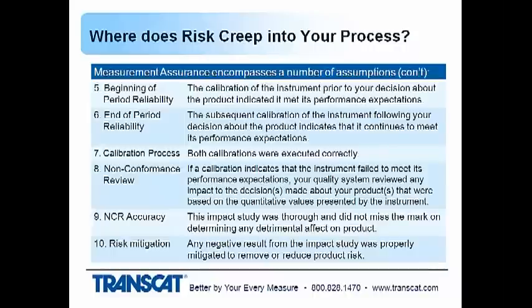Following the calibration, your non-conformance review. If your instrument failed to meet its performance specs, then your quality system probably has a review process in place that evaluates whether that had an impact to the decisions being made about the quality of your product, because that changes the quantitative values that you're relying upon. And then the accuracy of that nonconformance review. How thorough is it? Did it miss the mark on making sure that it evaluates whether those errors in the instrument actually had an impact on where it was being used? And then risk mitigation. Any negative result from the impact study and how that's mitigated to remove or reduce risk in your product.